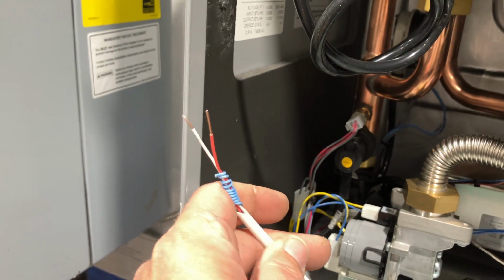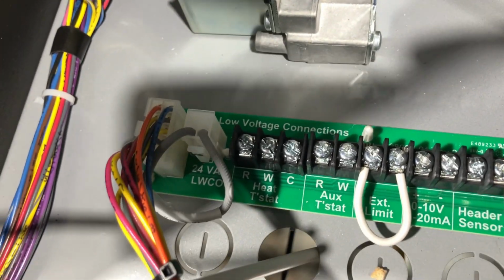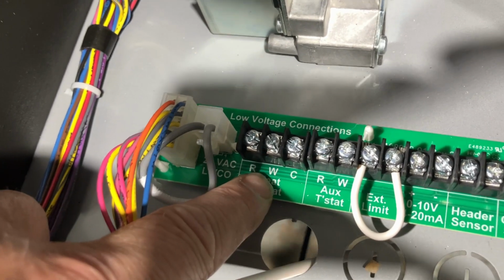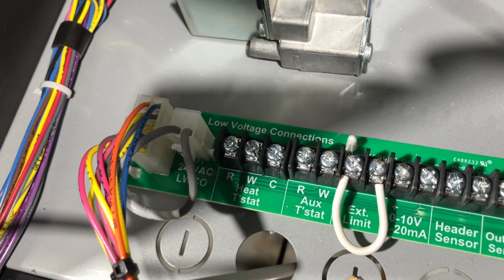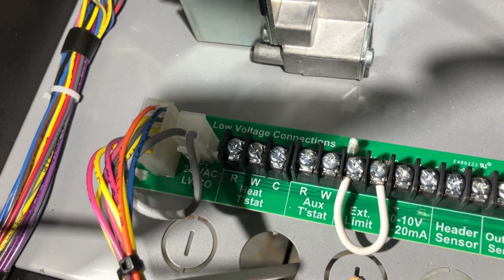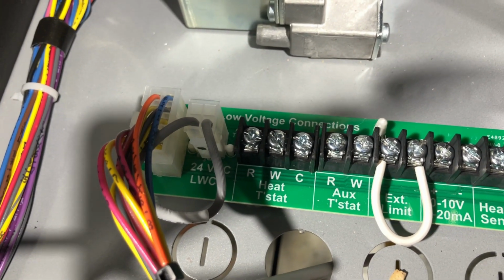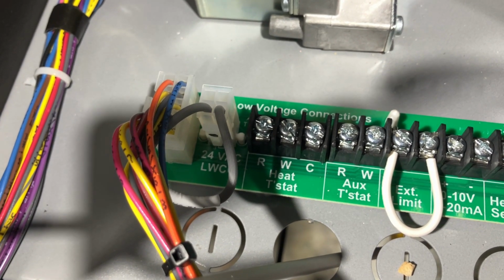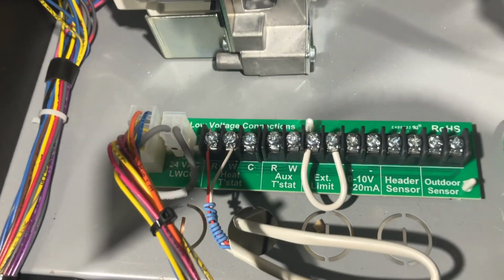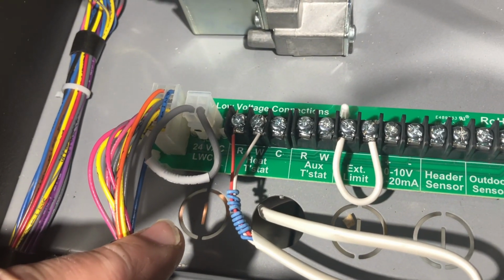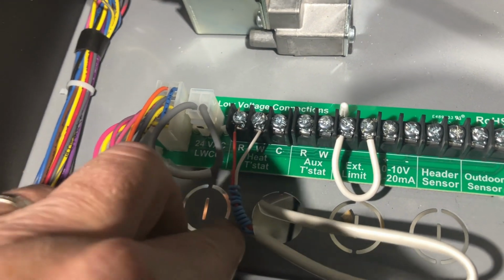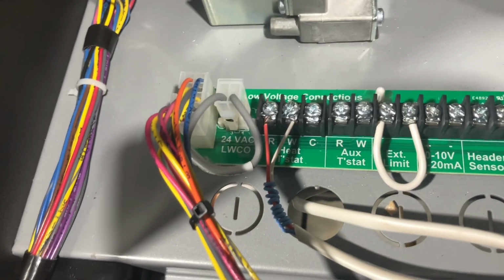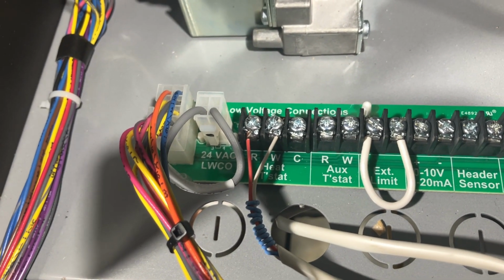Okay? Right. Now, we have 2 wires, R or red and white. Red and white, look at that, even tells you where it goes. We have thermostat right here. R, W, and C. Okay. If we had a Wi-Fi thermostat, we're going to use that common wire, or that blue wire, and wire all 3 wires. But we're just going to wire R and W. Right. Now, on other boilers, that's represented as TT, or 2 thermostat. Okay? So the red wire goes on R, the white wire goes on W. All right, we have the R and the W terminals wired, and they're noted as heat thermostat. On your boiler, it could be 2 thermostat, it could be TT, what have you, but that's that.